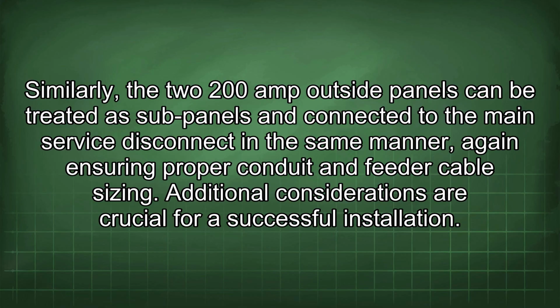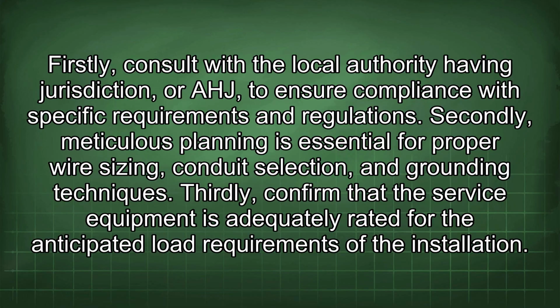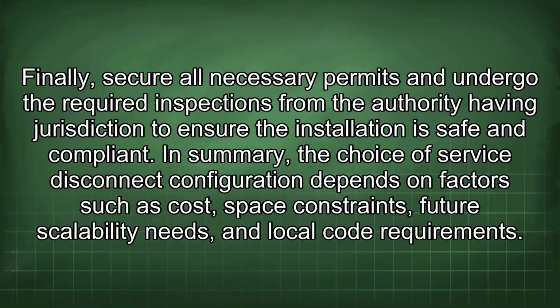Additional considerations are crucial for a successful installation. Firstly, consult with the local authority having jurisdiction, or AHJ, to ensure compliance with specific requirements and regulations. Secondly, meticulous planning is essential for proper wire sizing, conduit selection, and grounding techniques. Thirdly, confirm that the service equipment is adequately rated for the anticipated load requirements of the installation. Finally, secure all necessary permits and undergo the required inspections from the authority having jurisdiction to ensure the installation is safe and compliant.